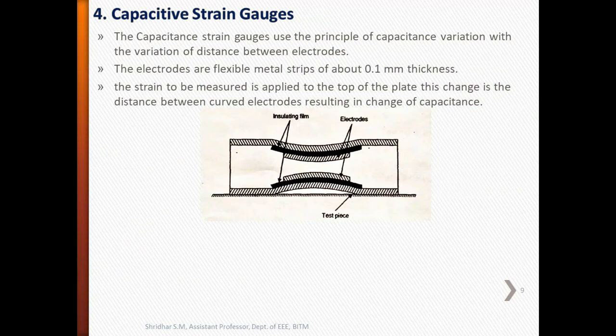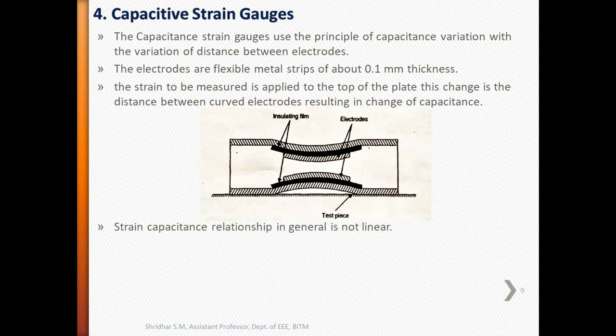Next we will discuss capacitive strain gauges. The figure shows a capacitive strain gauge. It uses the principle of variation of capacitance with variation of distance between electrodes. The electrodes are flexible metal strips of about 0.1 mm thickness. The strain to be measured is applied to the top of the plate, which changes the distance between the curved electrodes, resulting in a change of capacitance. The strain-capacitance relationship in general is not linear, but variation in dimensions and shape allow gauge characteristics to be chosen so as to match the range of capacitance to be measured with a good degree of accuracy.